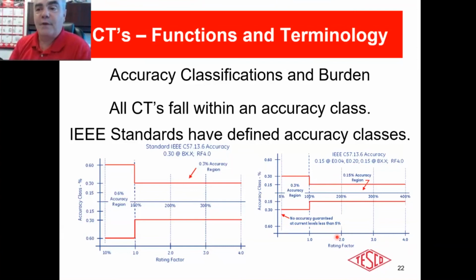Don't be too afraid of it. Just understand what it means. It means you can't stay at 6,000 amps for an extended period, if that's what it happens to be, at 6,000 to 5. All right. How much can you go for if it's rated at 0.8 thermal rating factor, and it's a 6,000 to 5? It means you can get up to 4,800 amps on the primary for an extended period without any problem. 4,800 amps or less, you're good. Start going above it, and you can't stay there for an extended period. All right.